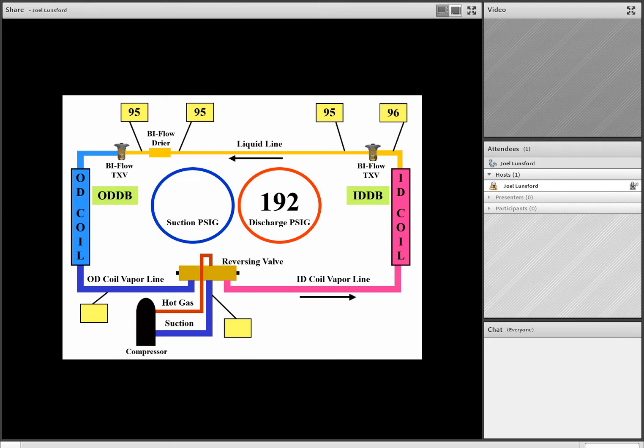The subcooling is much higher in the heating mode of operation because the indoor coil is full of refrigerant and it's a much smaller coil than the outdoor coil. So subcooling values will be higher on a heat pump in the heating mode. So let's do this example together. At 192 pounds of pressure for an R22 service call, it's about 98 degrees. About 98 degrees is a liquid pressure temperature conversion off of our R22 chart. Now we notice that the liquid line leaving the indoor coil is 96 degrees. And in our example, we only have 2 degrees of subcooling. The indoor coil is empty of liquid for whatever reason.